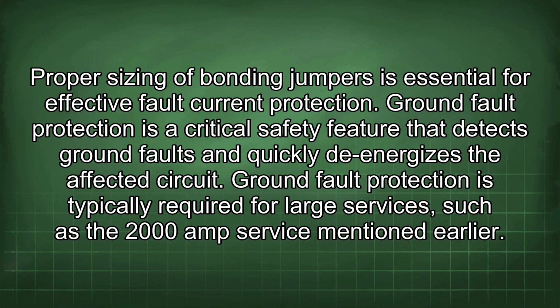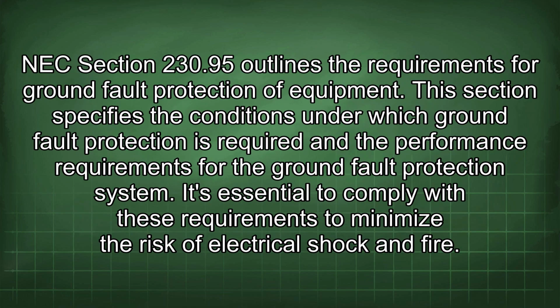Ground fault protection is a critical safety feature that detects ground faults and quickly de-energizes the affected circuit. Ground fault protection is typically required for large services, such as the 2000 amp service mentioned earlier. NEC Section 230.95 outlines the requirements for ground fault protection of equipment. This section specifies the conditions under which ground fault protection is required and the performance requirements for the ground fault protection system. It's essential to comply with these requirements to minimize the risk of electrical shock and fire.